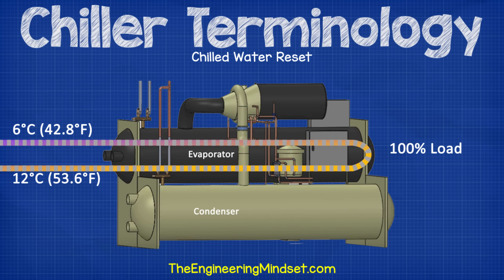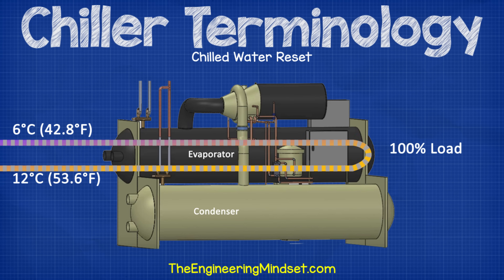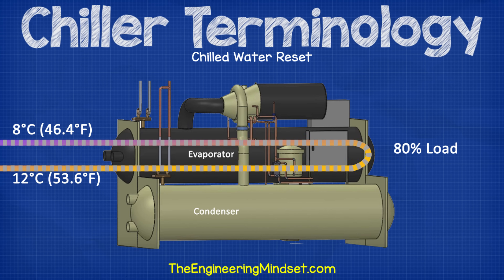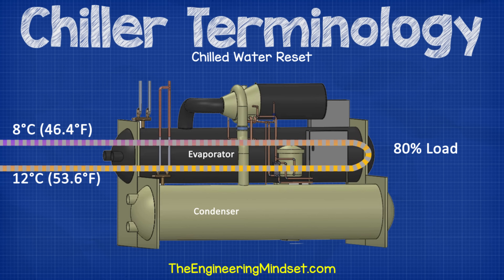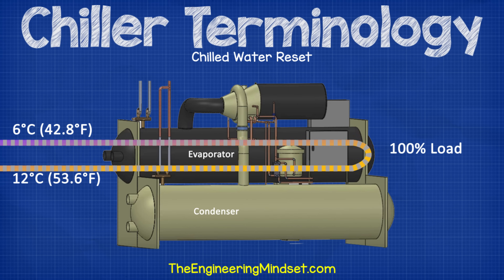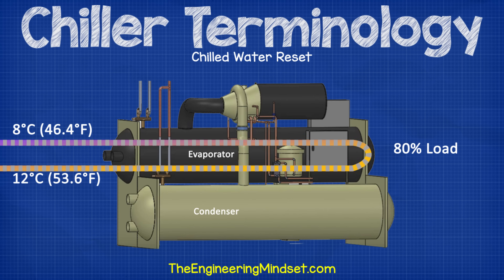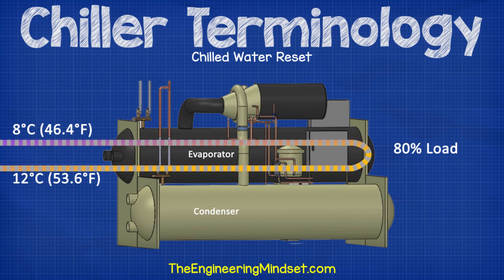Chilled water reset. This is a control strategy used to save energy. The strategy raises the chilled water supply temperature to reduce the lift, which will reduce the amount of work done by the compressor. This will also result in a higher return water temperature, which can lead to increased pump speeds in variable speed systems. It can also lead to low delta T syndrome and needs to be carefully analysed before being implemented.